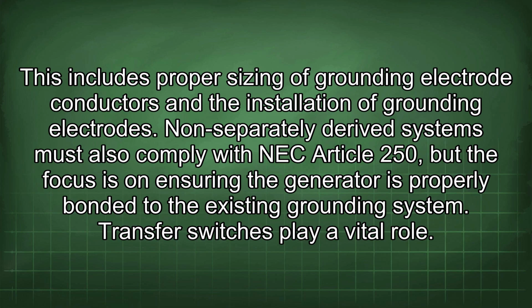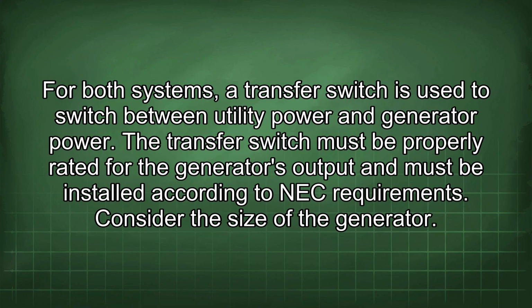Transfer switches play a vital role. For both systems, a transfer switch is used to switch between utility power and generator power. The transfer switch must be properly rated for the generator's output and must be installed according to NEC requirements.